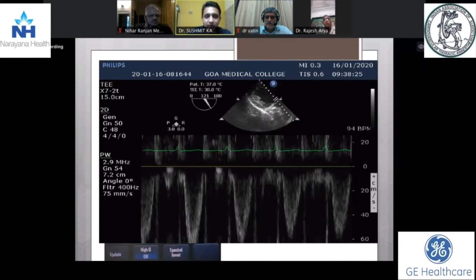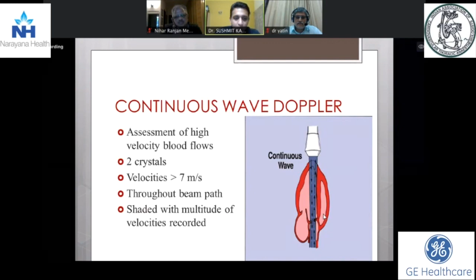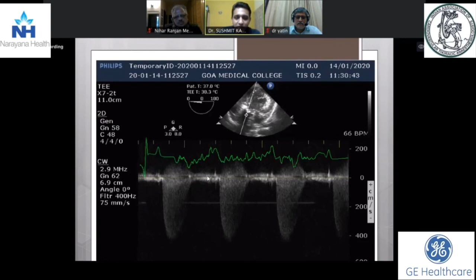Here, two separate crystals are used for transmitting and receiving. So velocities which are higher, more than 7 meters per second, can be evaluated. And it does not depend on any sample volume. It tells the highest velocities along the beam path. And it does not have a clear envelope. It shows a shaded envelope with a multitude of velocities. This is a flow through the normal aortic valve, but in case of severe aortic stenosis, the velocities will be much higher and can be easily evaluated.